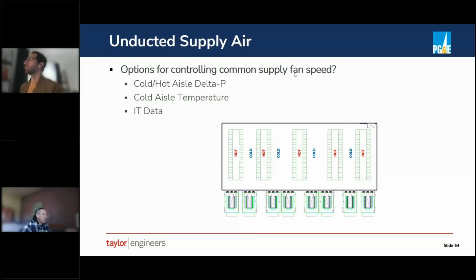Options for controlling common supply fan speed. Typically these would be air handlers pressurizing the space. And the most common way to control the speed or the flow of air from the air handlers is by measuring the differential pressure between the cold aisles and the hot aisles where the servers are pulling air. So if the servers are pulling more air than is being supplied, they will basically suck the cold aisles negative and pressurize the hot aisle, which means you aren't supplying enough air. If you speed up the supply fans so that they're supplying more air than the servers are pulling, then the cold aisle will become positively pressurized relative to the hot aisle.